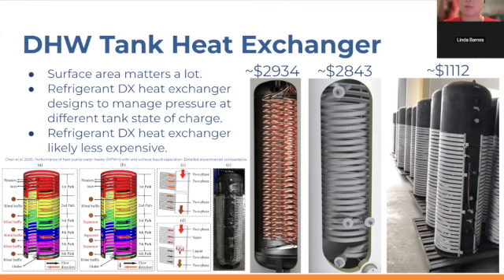But if you have cold water at the very top of the tank, then that refrigerant vapor will condense at the top, and that liquid will block the small holes of the orifice. That prevents the refrigerant vapor from going straight to the bottom of the tank, so you still get the top-to-bottom heating effect when the tank is very cold. But when the tank is only a little bit cold at the bottom, you have the efficiency of bypassing all the top heat exchanger to get the hot gas to directly heat the bottom of the tank. So you get the best of both worlds. And this game-changing design has really enabled a number of manufacturers to go with this route.